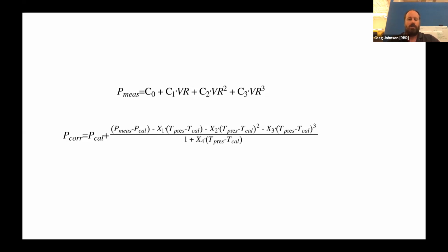This will only give you a pressure measurement that is accurate at the temperature at which that pressure sensor was deployed. And so in order to calibrate it across a range of temperatures so that we can achieve the datasheet accuracy, which is about 0.05% of full scale, and so depending on which pressure sensor you obtain, if you're using 20 dbar, it's 0.05% of that. If you're using 10,000 dbar, it scales up accordingly. However, the temperature effects are quite significant.